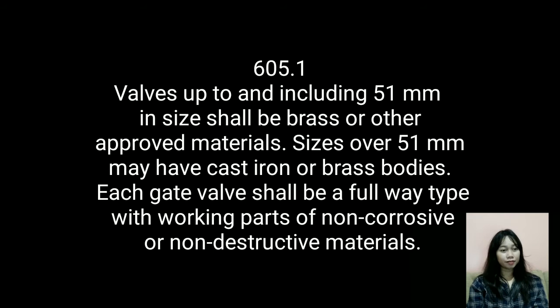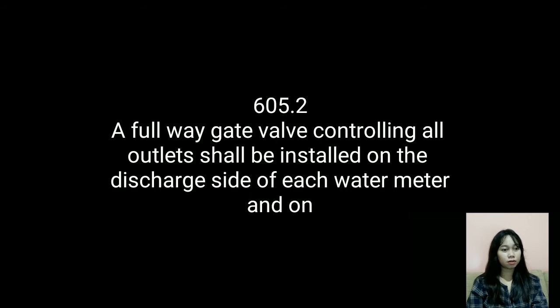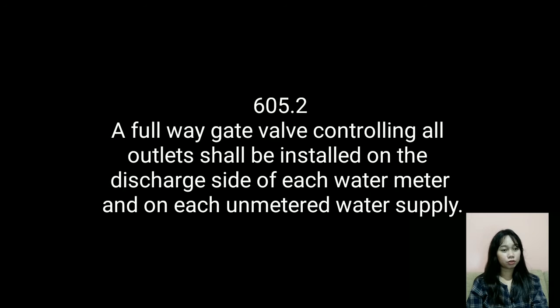In Section 605, valves up to and including 51 millimeters in size shall be brass or other approved materials. Sizes over 51 millimeters may have cast iron or brass. Each gate valve shall be a full-way type with working parts of non-corrosive or non-destructive materials.